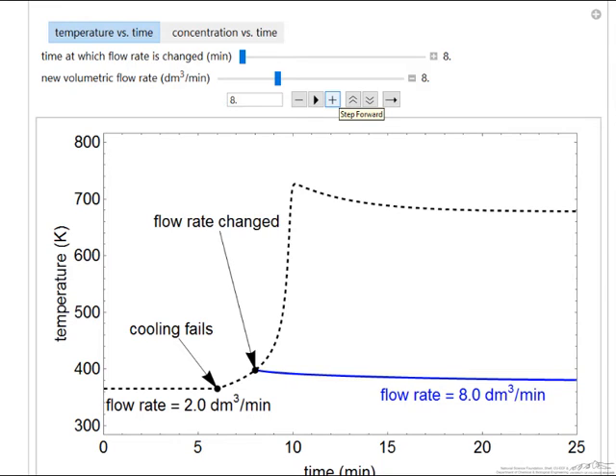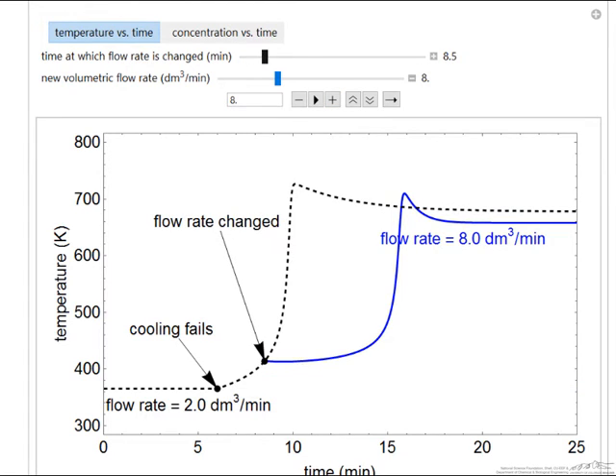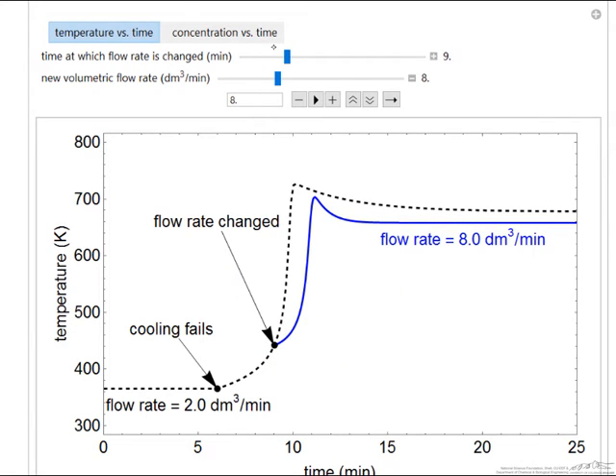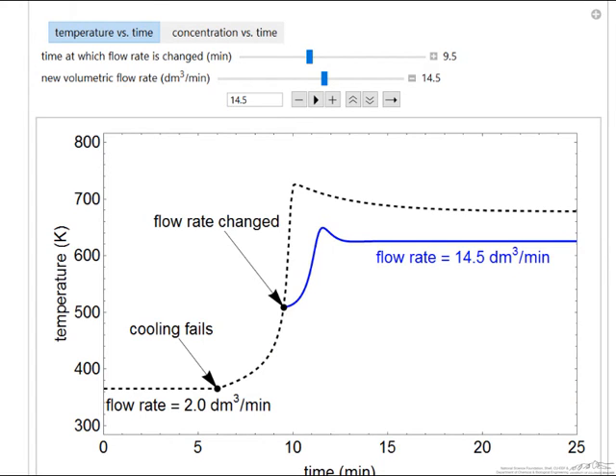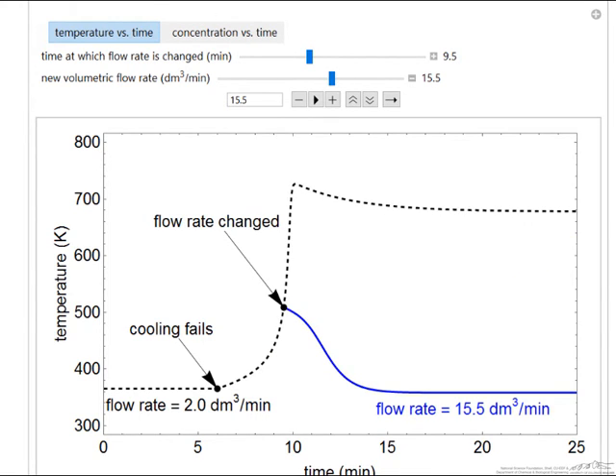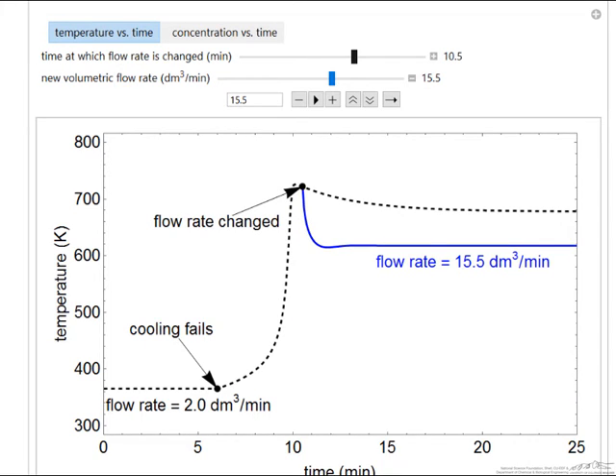If we look at the effect of the time at which we make this decision, if we wait longer—say 9 minutes—then we have to go to a much higher flow rate. If we wait a lot longer, we keep increasing the flow rate and we're able to compensate. Of course, if we wait when it's already at the maximum temperature, it's not accomplishing our goal of preventing the temperature overshoot.